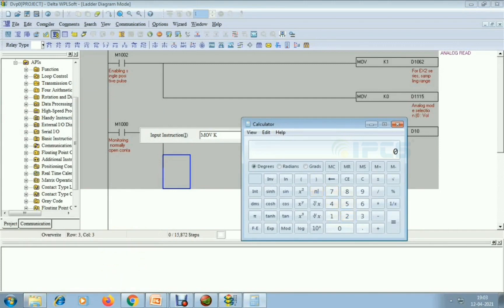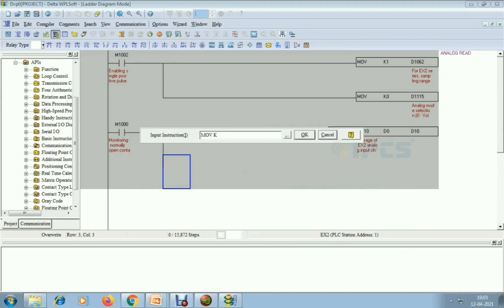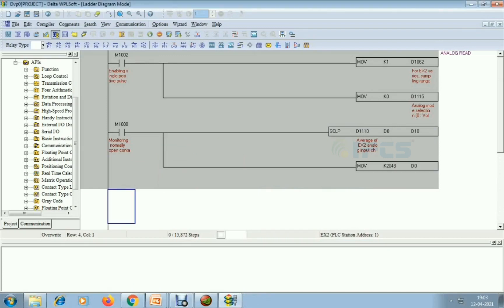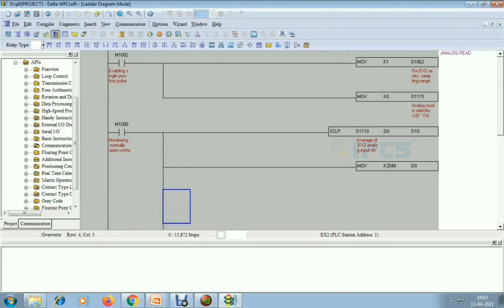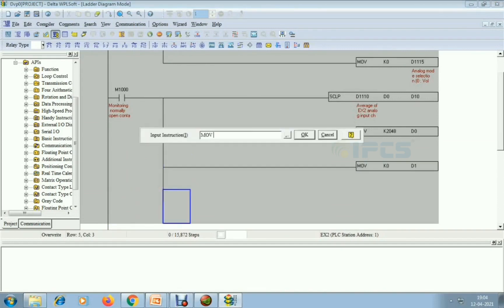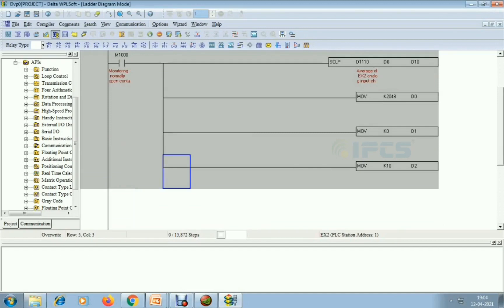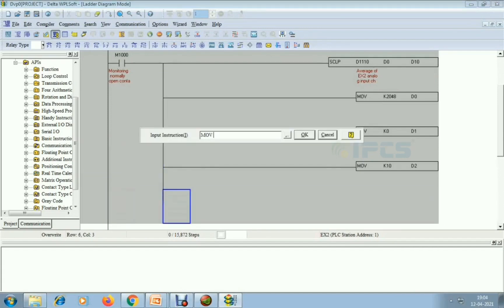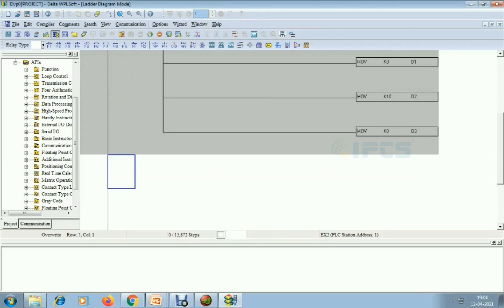So I am using the calculator: 2 to the power 11 gives a maximum value of 2048. I move K2048 to D0 as the maximum source value. Then MOV K0 to D1 for minimum source value. Maximum scale value is 0 to 10 volt, so I move K10 to D2, and minimum scaling value K0 to D3. This fills the four consecutive bits D0, D1, D2, D3 with min and max values.